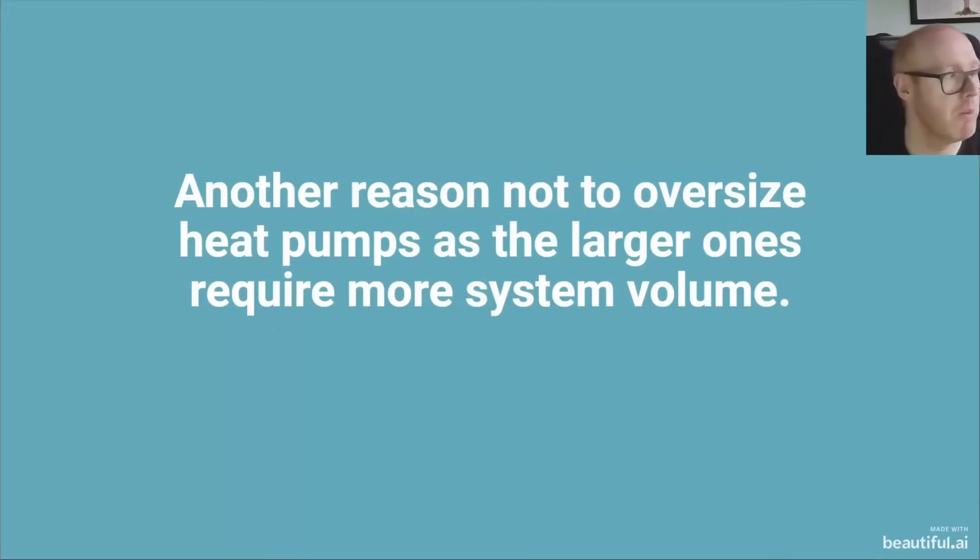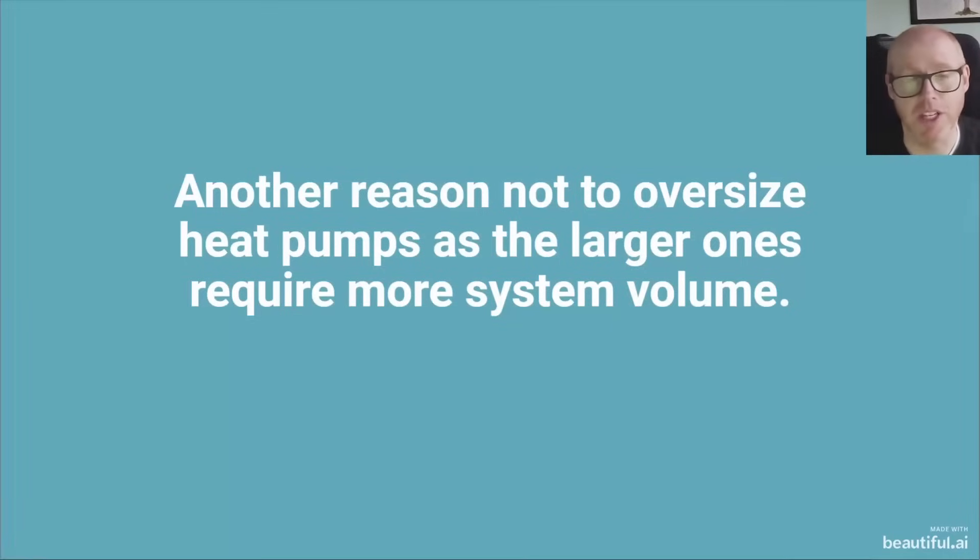If we look at the 12 kilowatts Arotherm Plus, that has a minimum system volume of triple what the 7 kilowatt does, so it goes from 55 litres up to 150 litres. So the difference between a 7 kilowatt heat pump and a 10 kilowatt or 12 kilowatt heat pump in terms of minimum system volume is quite substantial and significant.